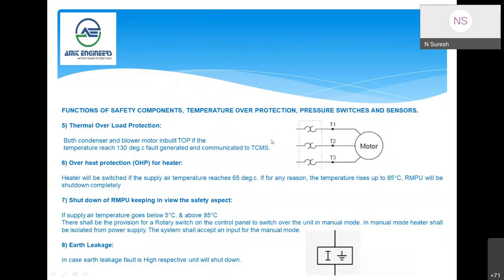Each motor has a thermal overload protector built into the motor. That is 130 degrees is the temperature. If the motor temperature, that is the stator temperature, reaches 130 degrees, the motor will switch off and a fault signal will be given to the system. There is an overheat protection, OHP. As I explained, there are 3 levels of protection in the system: 65 degrees, 85 degrees, and fusible is 130 degrees.